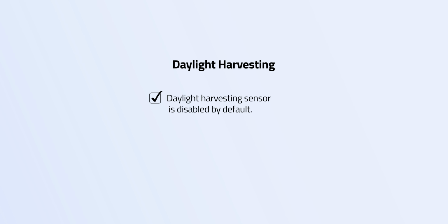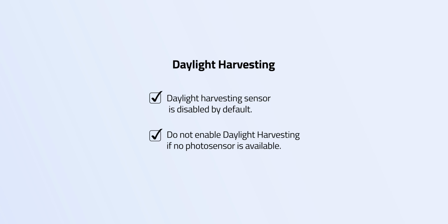It's worth noting that the daylight harvesting sensing function is disabled by default. We'll shortly be looking at how to enable it and how to set thresholds both manually and automatically with auto-calibration. Do not enable daylight harvesting if no photosensor is installed or connected. Otherwise, it may keep dimming randomly because the light cannot detect the correct ambient light level.